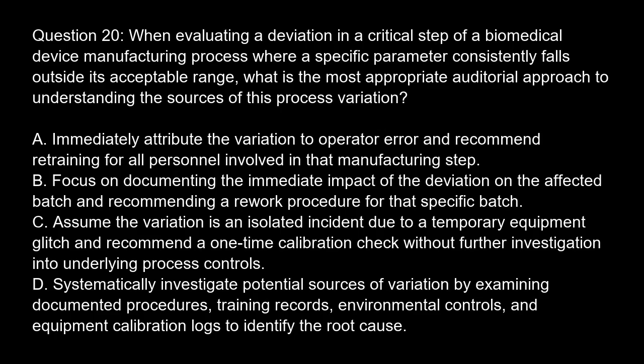Question 20. When evaluating a deviation in a critical step of a biomedical device manufacturing process, where a specific parameter consistently falls outside its acceptable range, what is the most appropriate auditorial approach to understanding the sources of this process variation? Option A. Immediately attribute the variation to operator error and recommend retraining for all personnel involved in that manufacturing step. Option B. Focus on documenting the immediate impact of the deviation on the affected batch and recommending a rework procedure for that specific batch. Option C. Assume the variation is an isolated incident due to a temporary equipment glitch and recommend a one-time calibration check without further investigation into underlying process controls. Option D. Systematically investigate potential sources of variation by examining documented procedures, training records, environmental controls, and equipment calibration logs to identify the root cause.